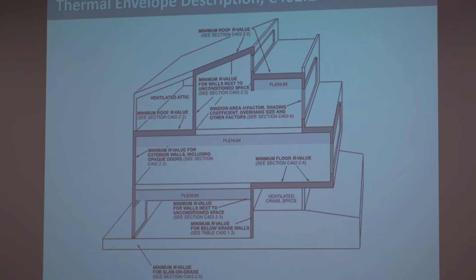We've got walls. This diagram I think is really helpful. It shows we've got two sections that might be inside what we would think of as the building envelope. We've got a ventilated attic and a crawl space. But notice the dark line is inside of there. Those are not mechanically conditioned spaces, so they're considered outside the building envelope. And specifically the crawl spaces we find are often missed when architects are detailing some of the thermal envelope because you just sort of forget that the floor there, even though you think it's over part of the building, is actually not part of the thermal envelope.